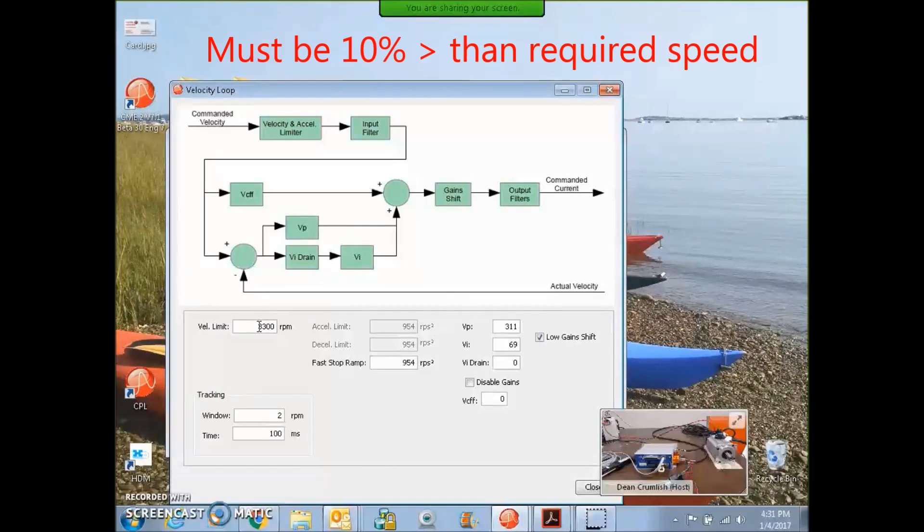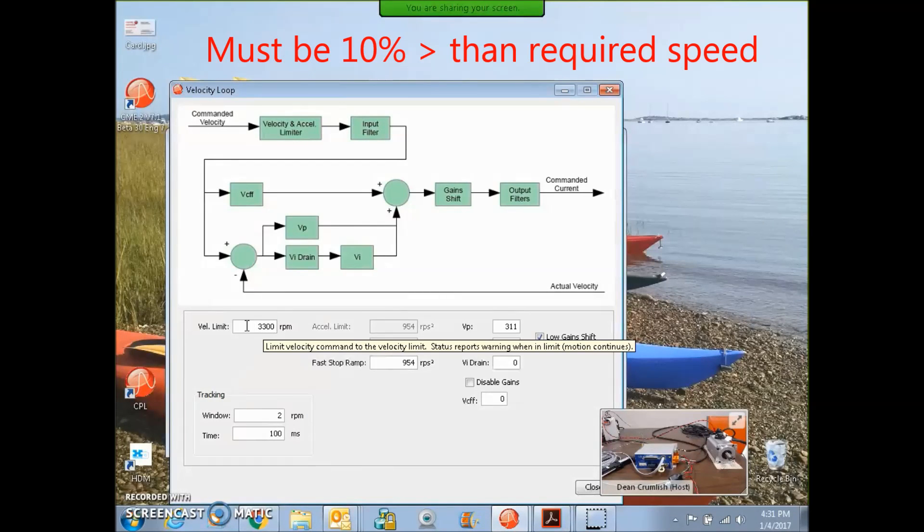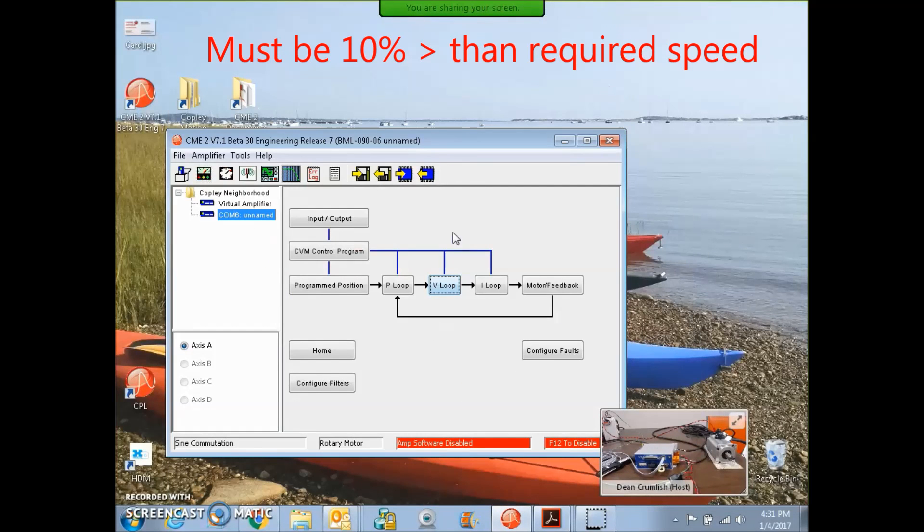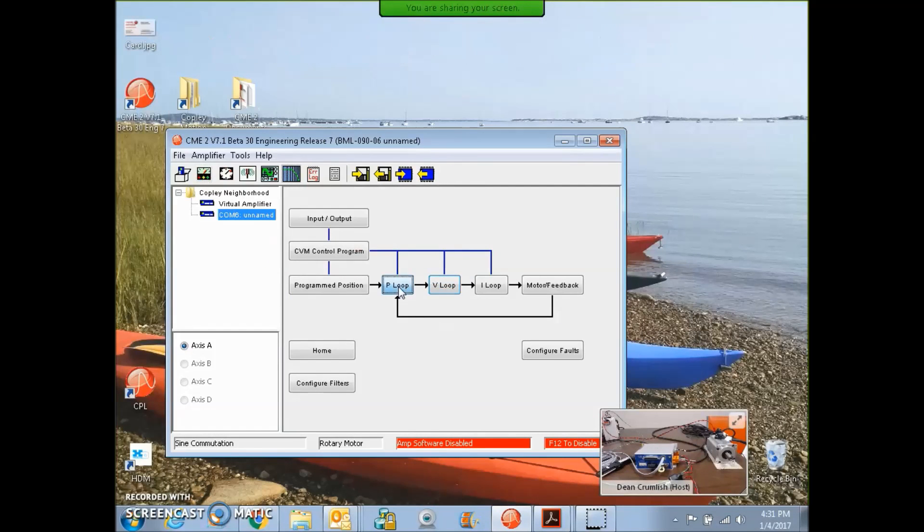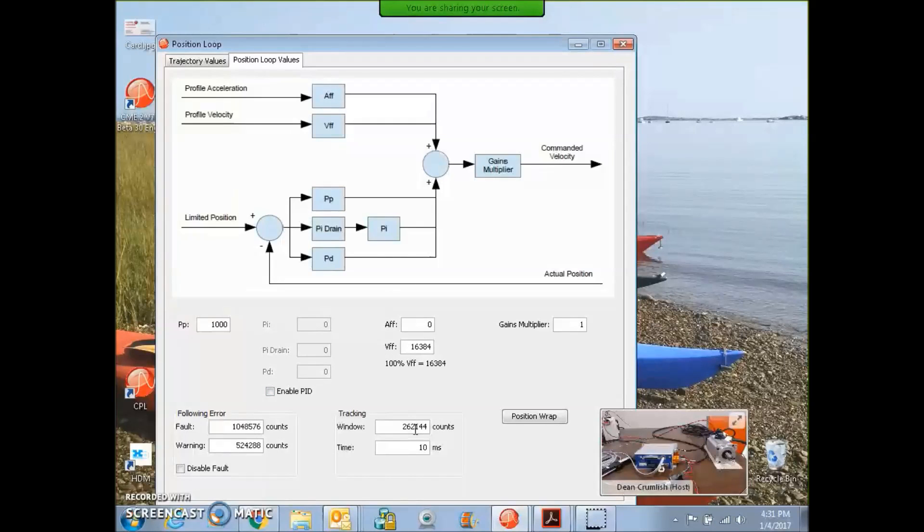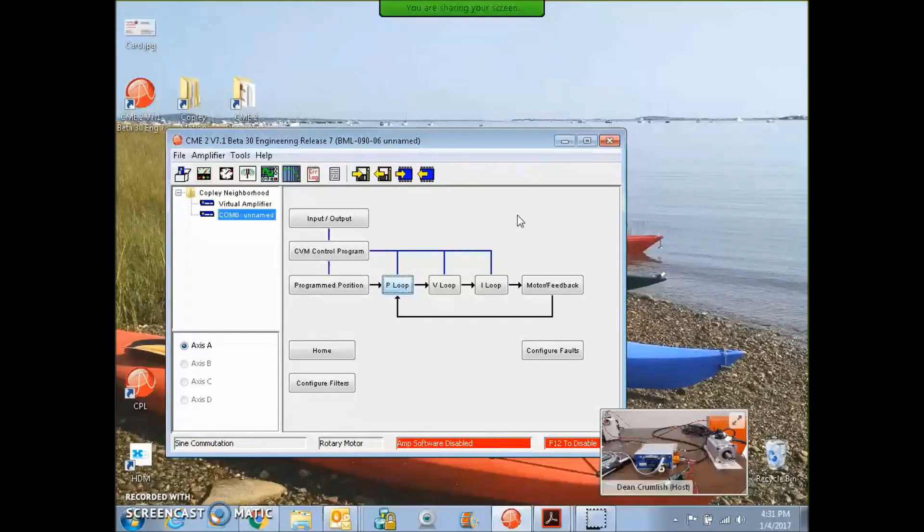On the V-loop screen, I gave it a little faster than the rated for the velocity limit, and we'll check out the gains from the math model, given the inertia. Position loop gains look pretty good. Tracking window's kind of high, but it's a million counts per rev, so we can change that later.